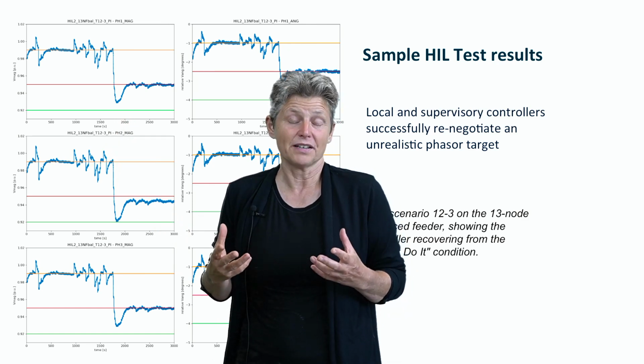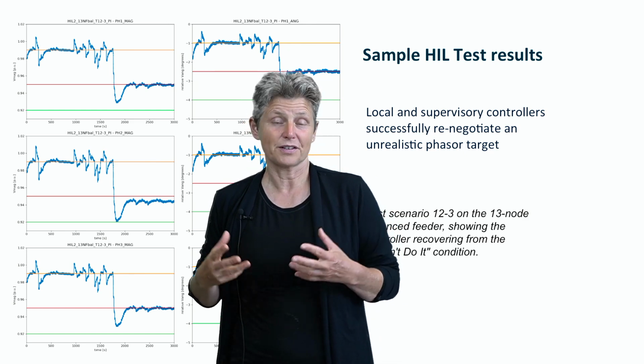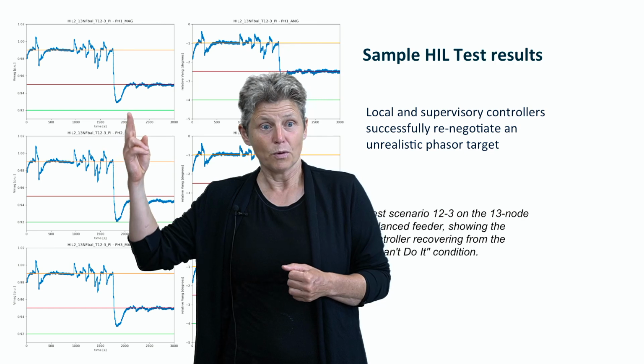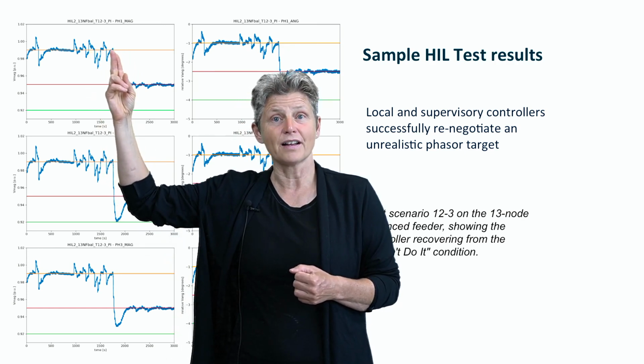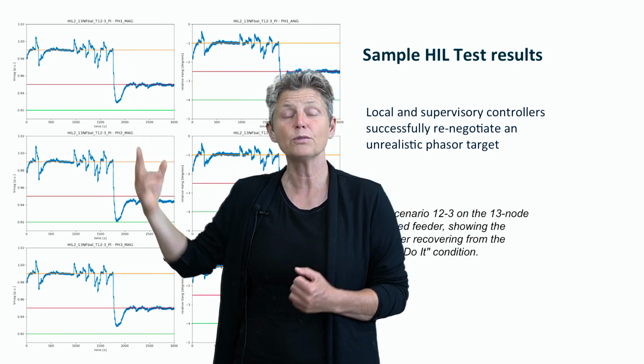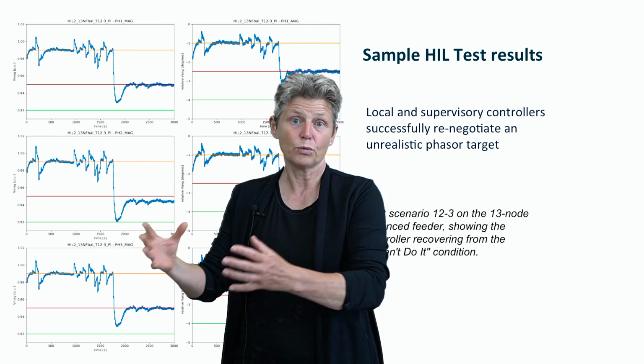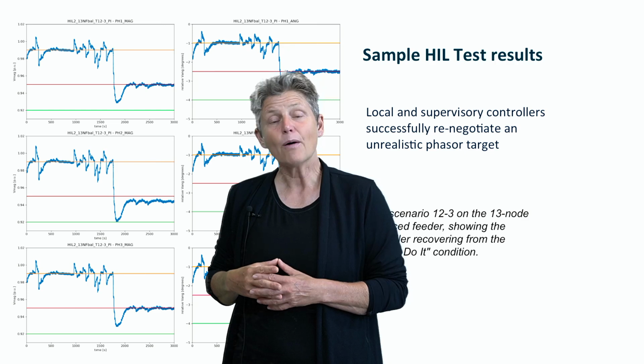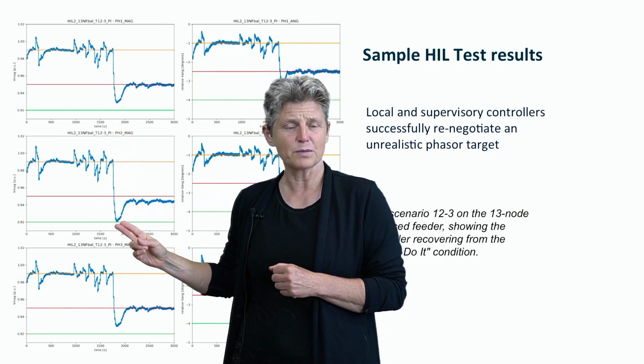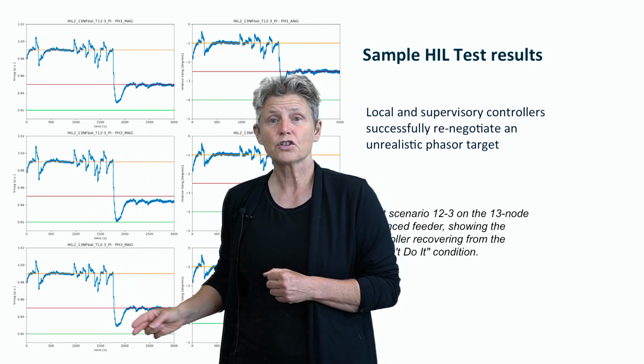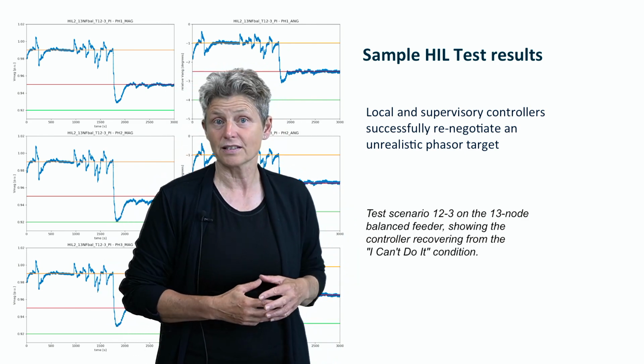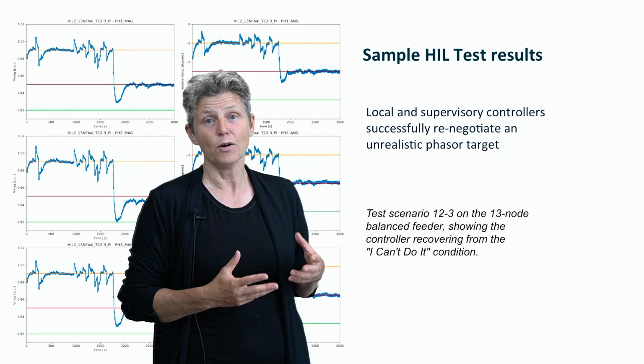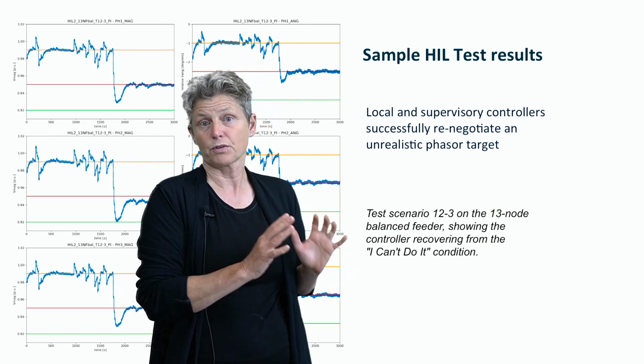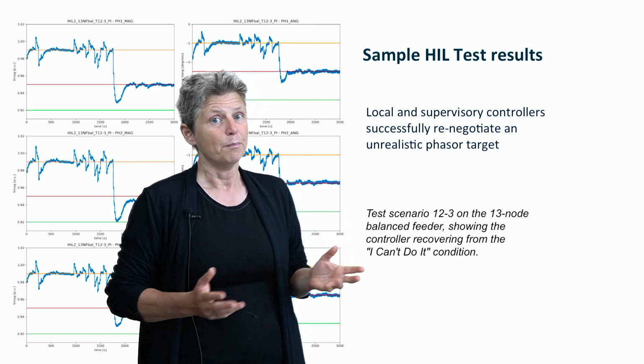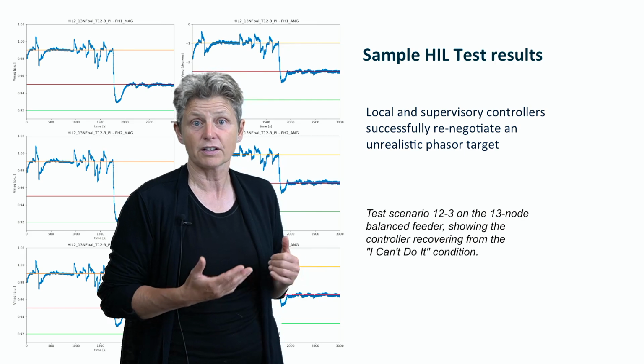So again, not really realistic, but what we have here for the actuators are some batteries, which when they see that, well, wait a minute, our voltage phasor was here at 0.99 per unit magnitude, and now we're supposed to get it down to 0.92. That means we need to increase load. We need to charge up the battery as much as we can. That wasn't possible on all three phases, so we got close here on phase B, but on phase A and C, couldn't quite get there. So that's when the local controller sends back an "I can't do it" signal to the supervisory controller to say, hey, we're trying, we're doing our best, we're driving the system as far as we can in the direction that you told us to, because that's presumably where we're going to be safe and steady, but we can't get there, so please recalculate the target and give us something more realistic.